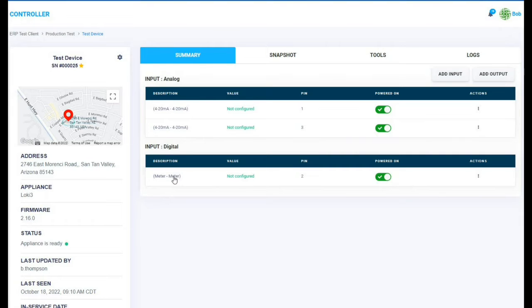Now let's show you how to add a Modbus probe. I mentioned before that you must program each probe separately and go to your controller in between each time. That's because if you hook up all three Modbus probes at once, your controller will simply see three probes with the same slave address and not know which one you want. Normally, a factory sets a default setting of 240 as a slave address, so by doing these one at a time, the controller will know what you want to do.